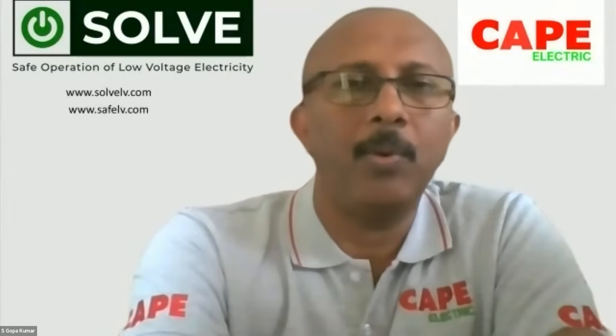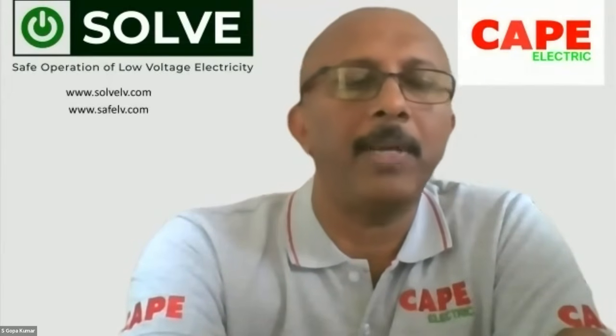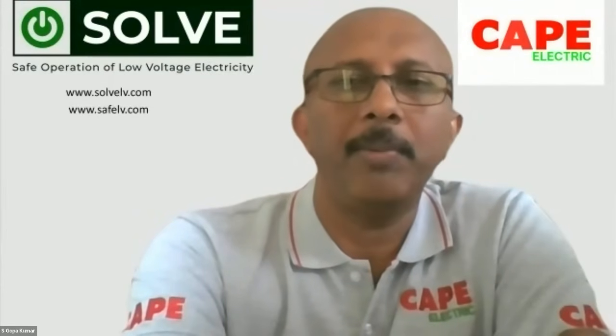Okay, moving to the next question. Morgan Mulenga is asking, how do I identify class 2 copper wire? At the moment, it's very difficult. Once this becomes popular, of course, the manufacturer will put it on the label or print it on the cable. First, there should be a demand. People should start asking for class 2 wire. Once there is a demand, the market decides, and automatically the manufacturer will put all these markings. At the moment nobody asks, so there is only one type of wire available, which is class 5. So you don't need to print or tell that it is class 5.